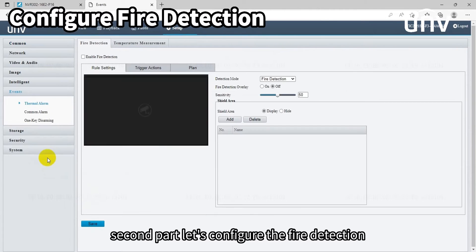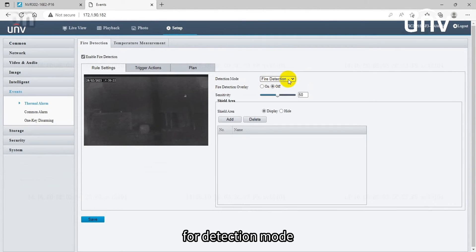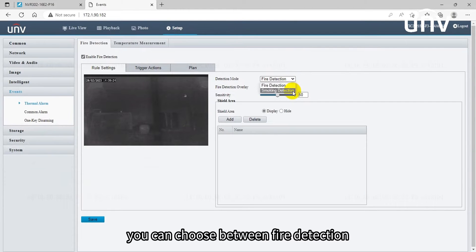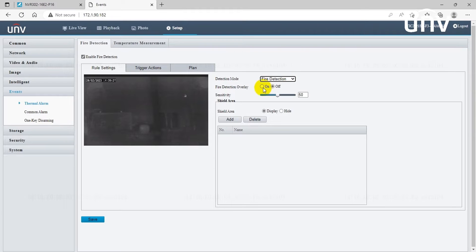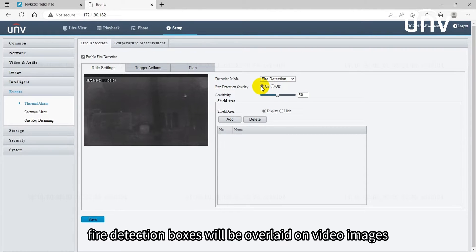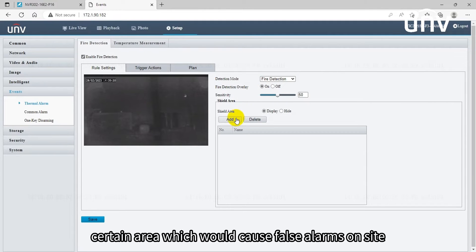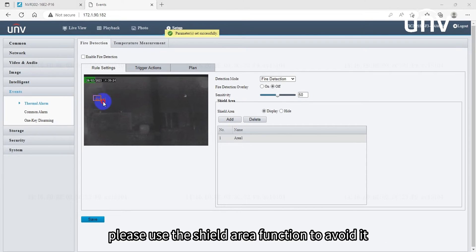Second part, let's configure the fire detection. For detection mode you can choose between fire detection or smoking detection. When enabled, fire detection boxes will be overlaid on video images. If there is a certain area which would cause false alarms on site, please use the shield area function to avoid it.